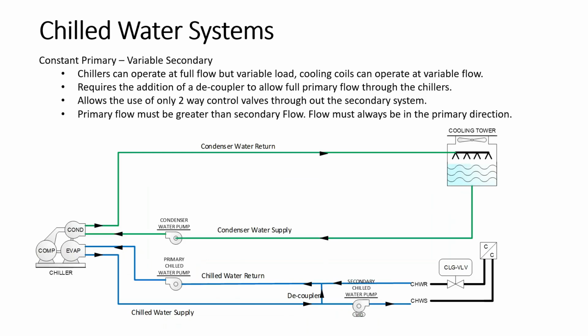Now in this case, we have a constant primary and a variable secondary. So we keep flow the same on the chiller all the time, but we vary the flow going out to the coils. We still have to have a decoupler to make this work. However, because of the primary side, that pump will pump water to the chiller through the decoupler and keep that loop going at a constant flow.